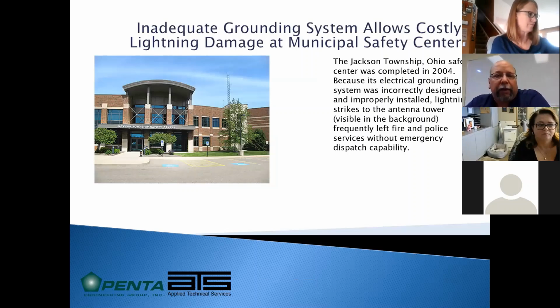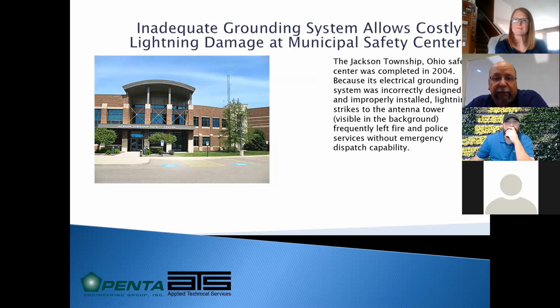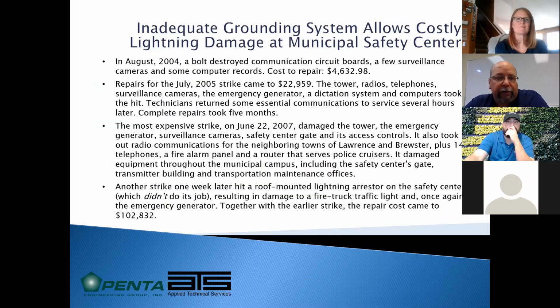Looking around, a lot of our clients really want to know: if it costs X number of dollars to install a lightning protection system, what are the costs if I don't have one? What kind of damage can it really do? This is an example of a municipality in Ohio. They did install a lightning protection system, but they had some deficiencies in the way it was grounded, as well as some deficiencies in a radio tower and the grounding plan. And they got struck several times.